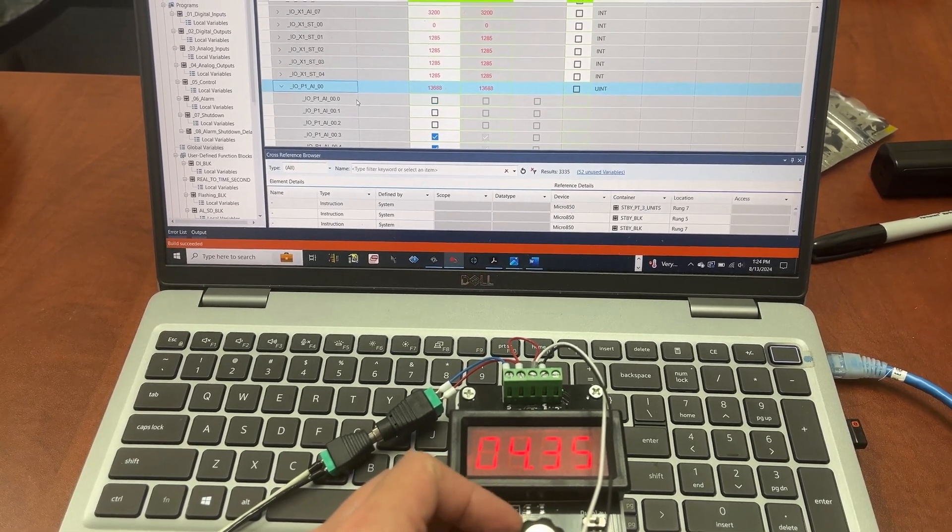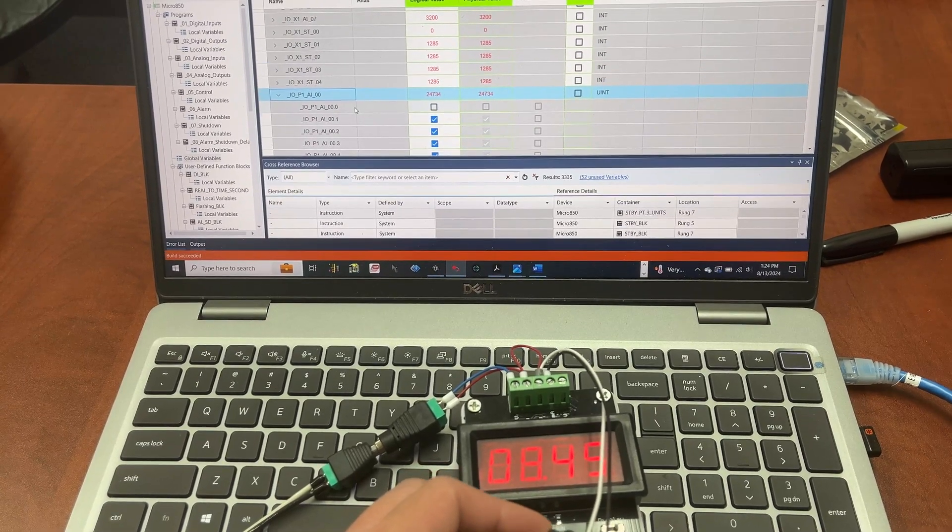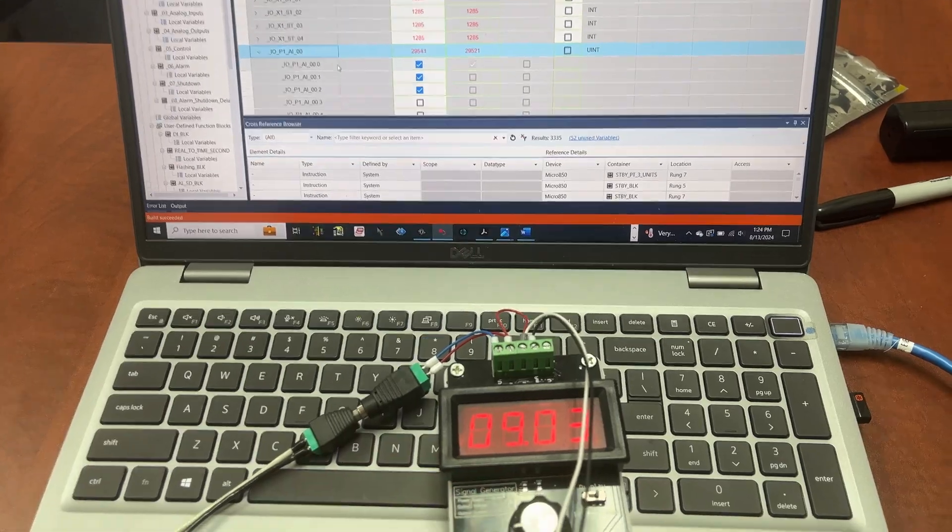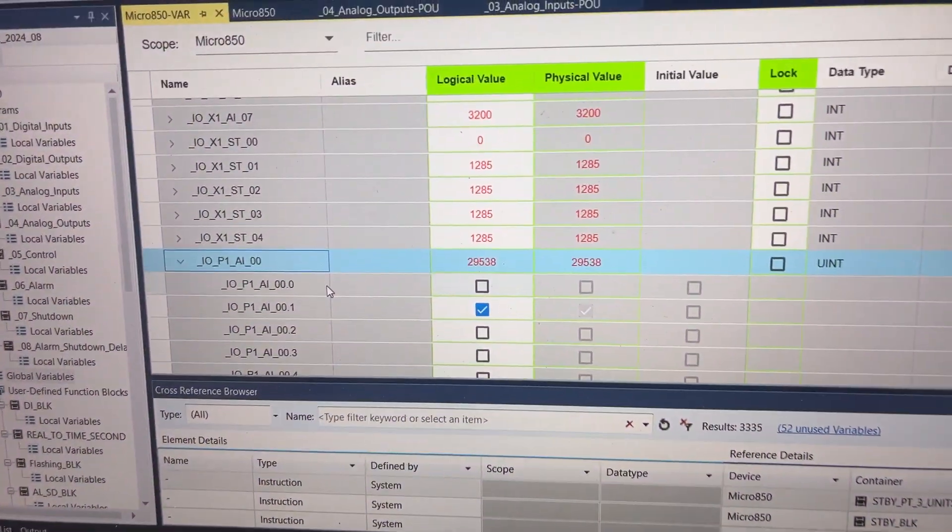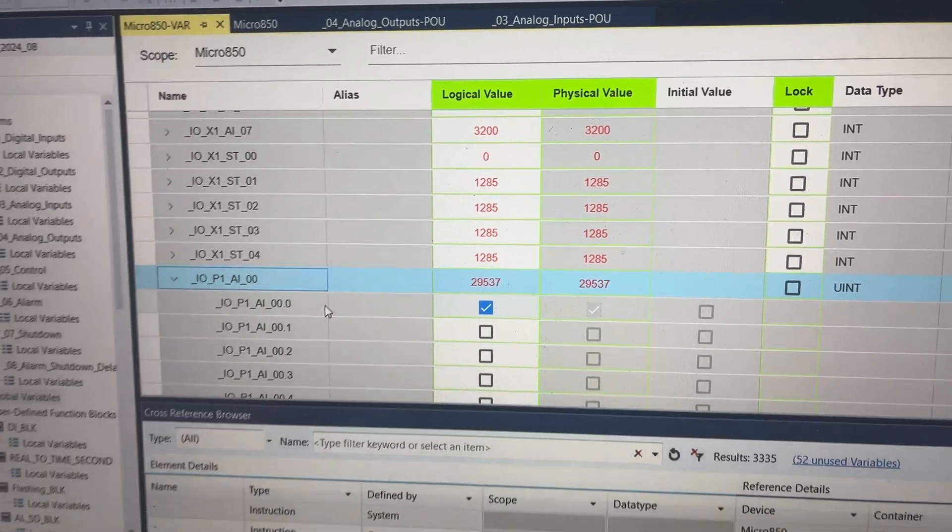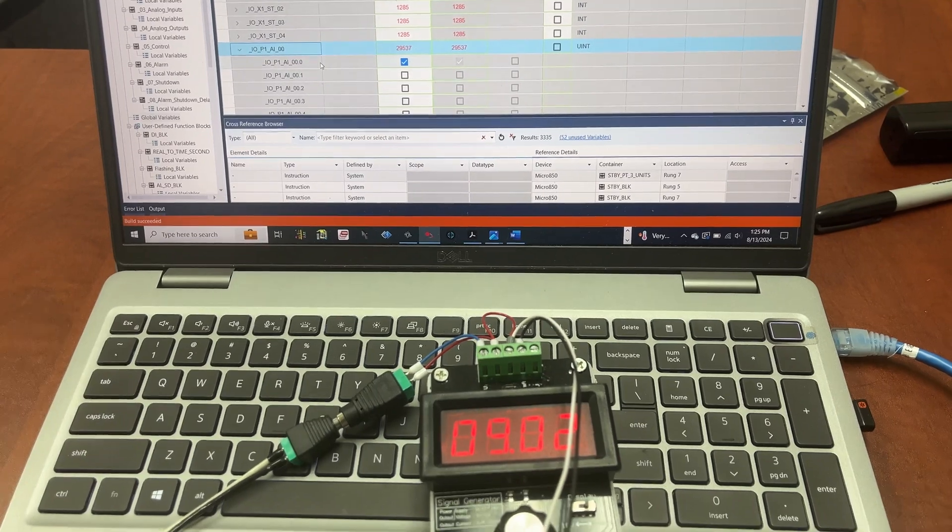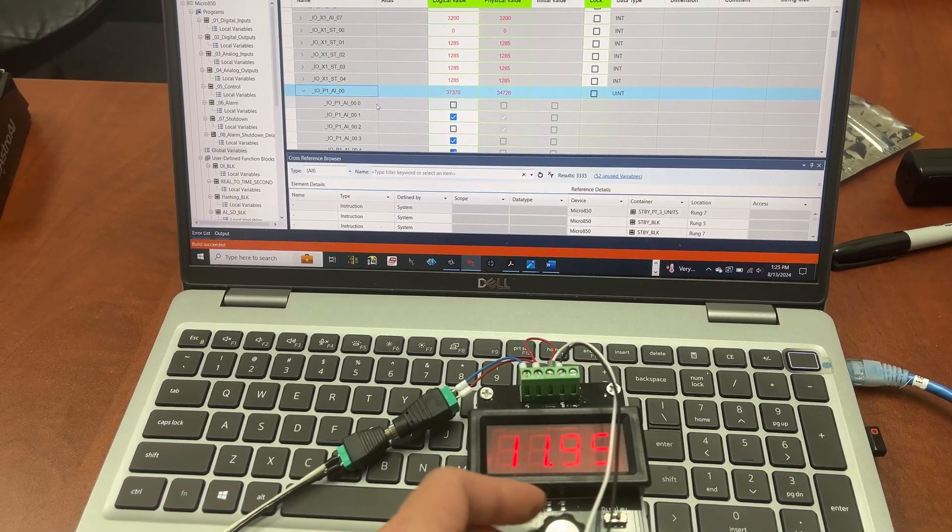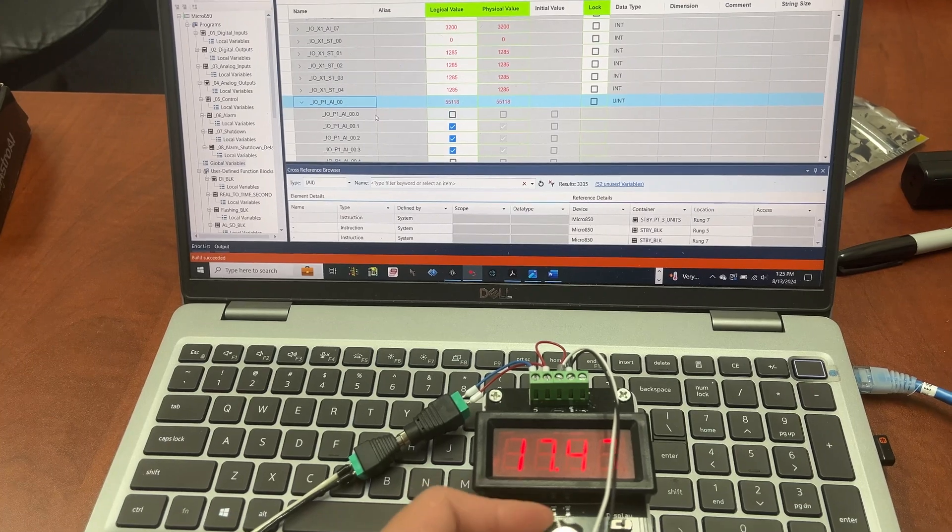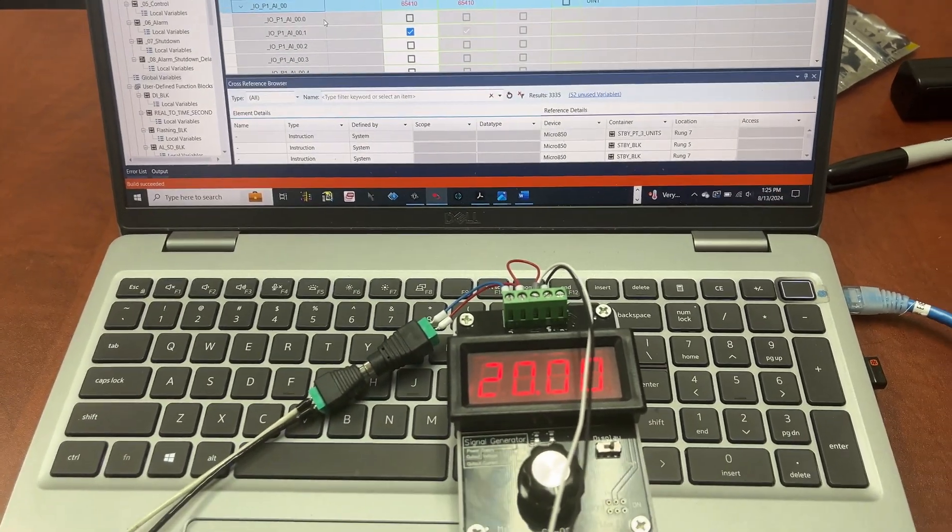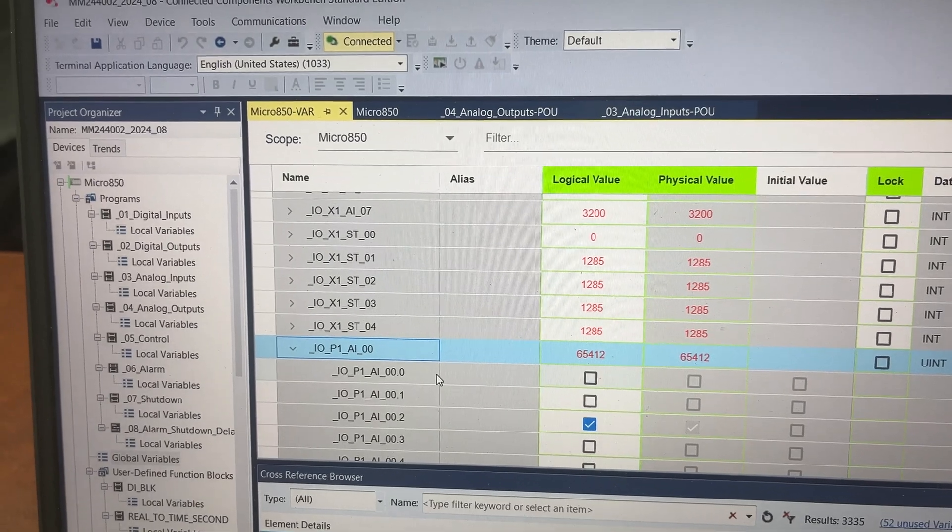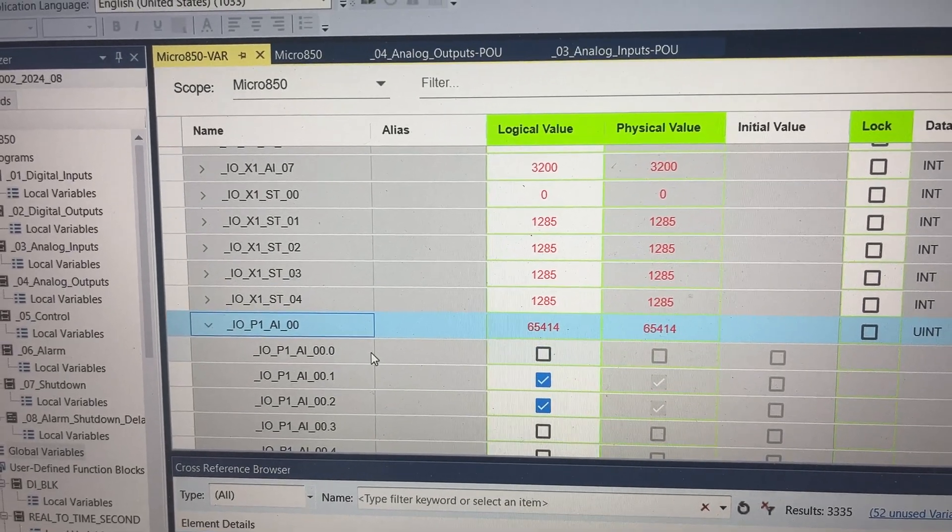If we increase the analog input to 9 milliamp, the PLC tag value is 29,537. If we keep going up all the way to 20 milliamp, the PLC tag value will be 65,414.